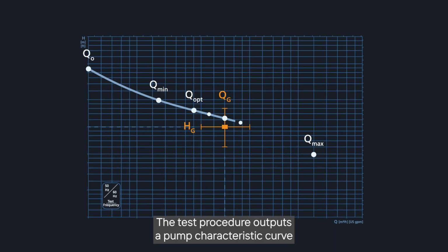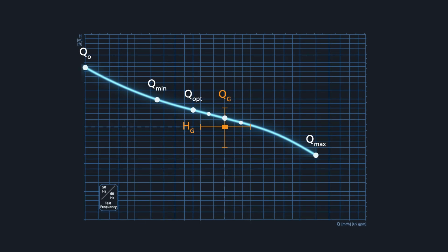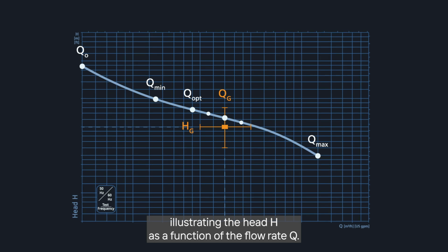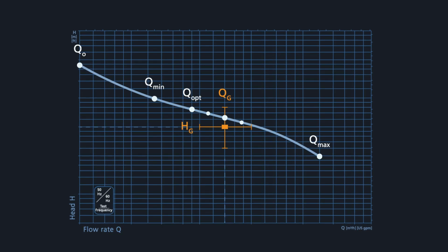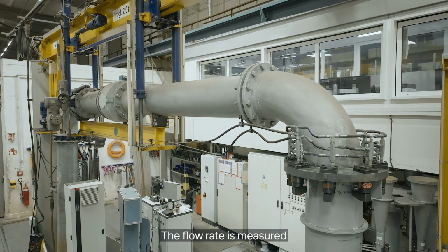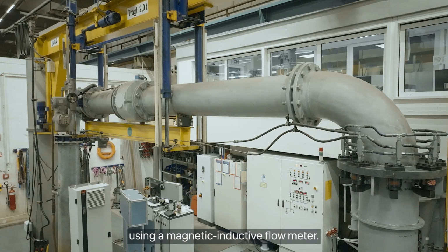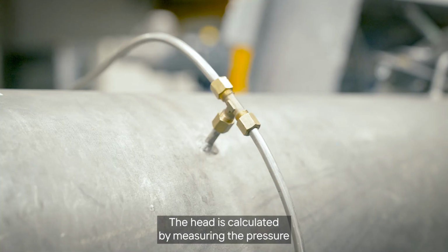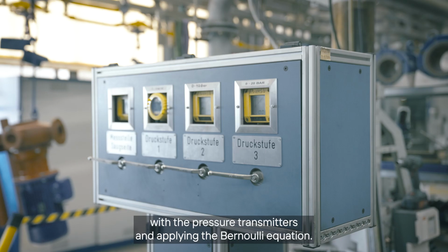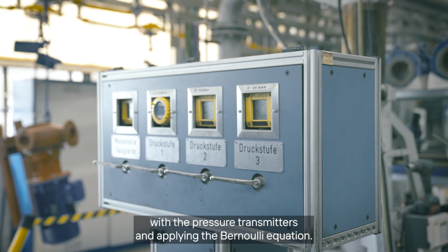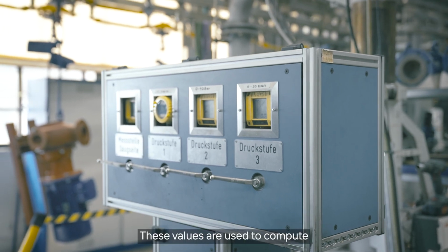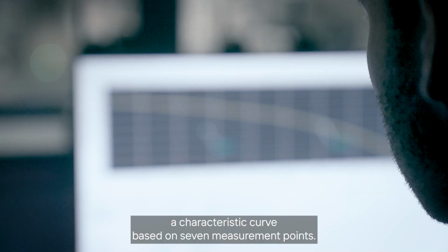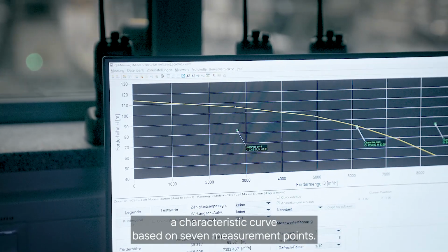The test procedure outputs a pump characteristic curve illustrating the head H as a function of the flow rate Q. The flow rate is measured using a magnetic inductive flow meter. The head is calculated by measuring the pressure with the pressure transmitters and applying the Bernoulli equation. These values are used to compute a characteristic curve based on 7 measurement points.